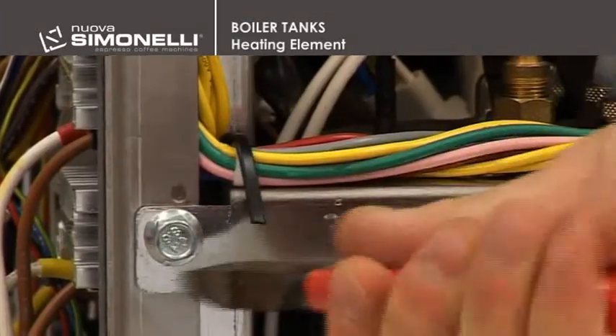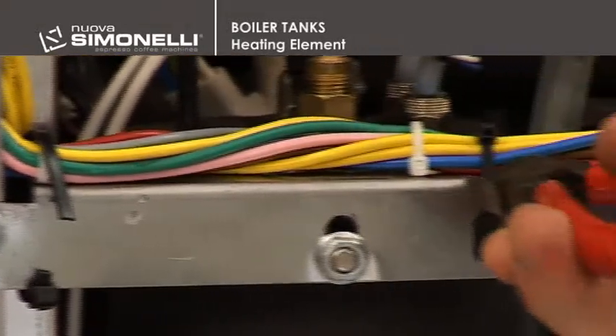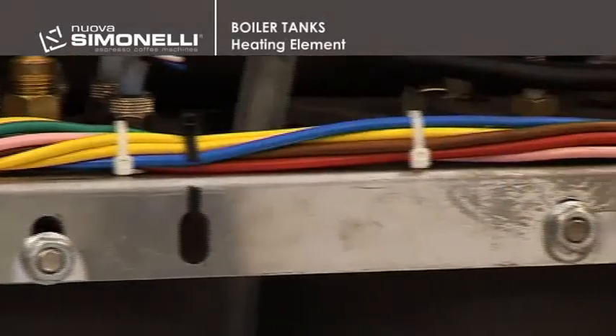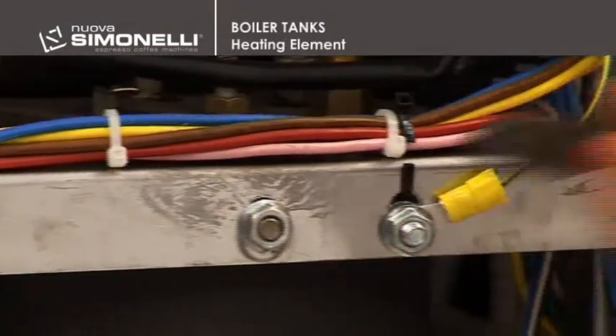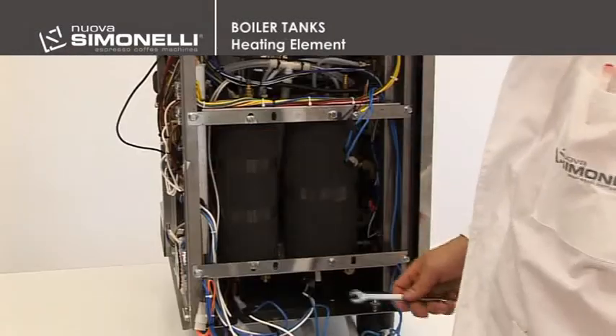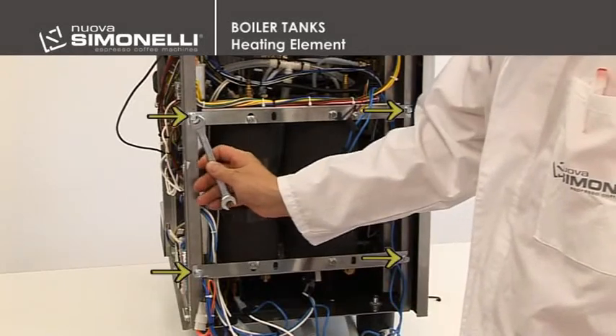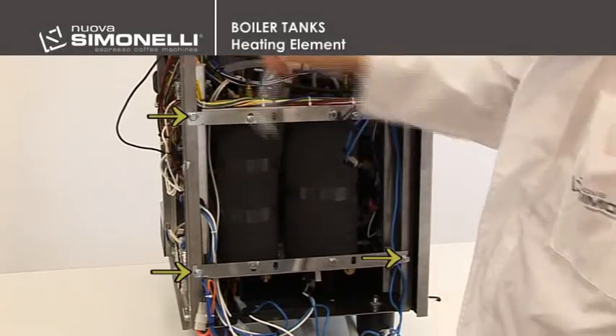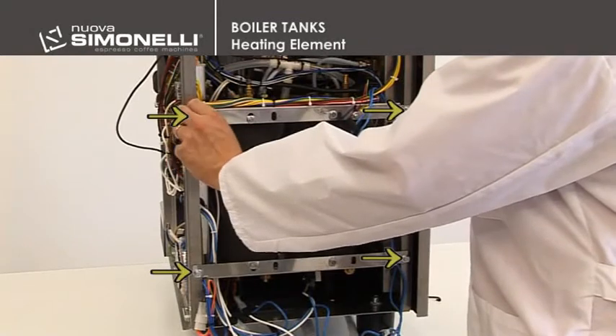Take off the clamps on the center bar of the bar panel and free the wires. Then, using a 10 mm wrench, take out the 4 screws securing the 2 boiler tank support bars to the frame.